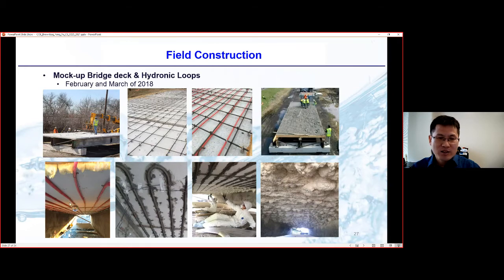The other method is external heating, which can be implemented on an existing bridge. We apply cement mortar between the PEX pipe and the concrete deck to increase thermal contact and make heat transfer more efficient. After placing the PEX pipe, we cover it with polyurethane insulation material to prevent heat loss to the bottom, to the environment. We want the heat to go directly to the top.